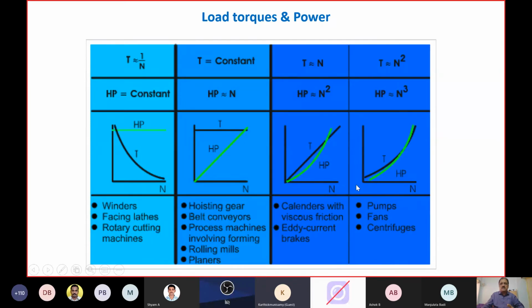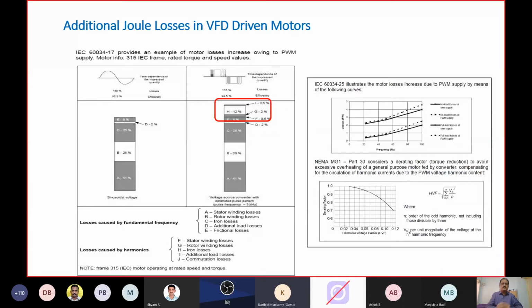So this has to be understood, followed by torque equal to constant. Here, energy saving may not be much, but there will be smooth starting and smooth stopping. So for some machines like conveyors, or even some applications where precise stopping and starting of the machine is needed, a VFD would be a good choice. So the best choice is torque proportional to N square, followed by constant torque. This has to be understood as a principle for applying VFDs with motors.